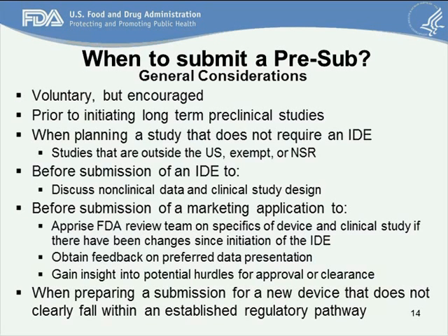We recommend talking to us before planning a clinical study that does not require an IDE. This would be studies that are either conducted entirely outside the U.S., that are exempt from the IDE requirements, or are non-significant risk and therefore exempt from an IDE application. It would be a good idea in those cases to get some feedback to make sure that the clinical study is going to answer the questions you're hoping it will answer for you.